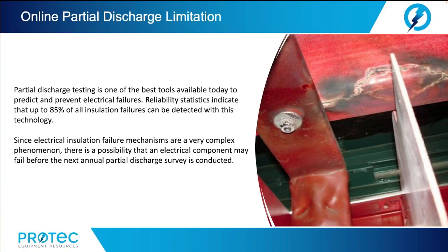Also, cross-linked polyethylene cable may contain water trees. For the most part, these water trees do not present an immediate concern. However, certain electrical events such as lightning or switching surges may initiate the water tree into a rapidly occurring electrical tree and thus a fault. Supplemental offline tests such as tan delta can be performed to evaluate cables for contamination such as water treeing. Also, periodic monitoring should be considered for all critical circuits.